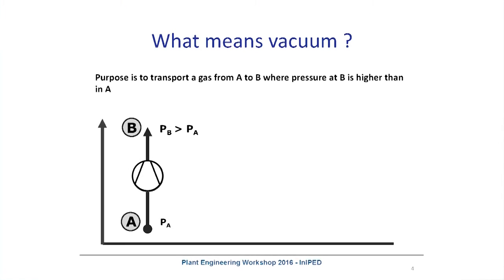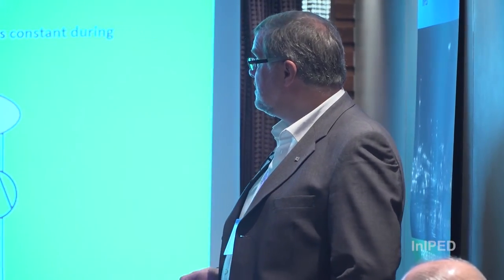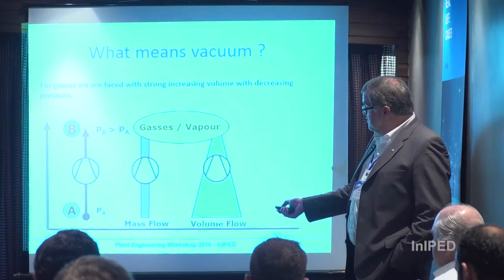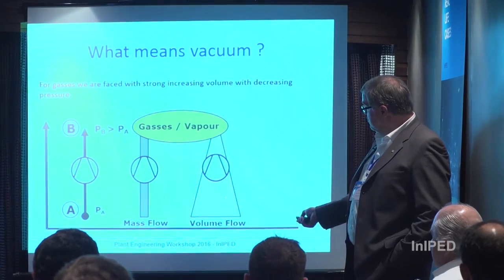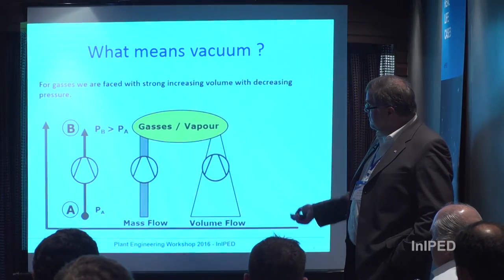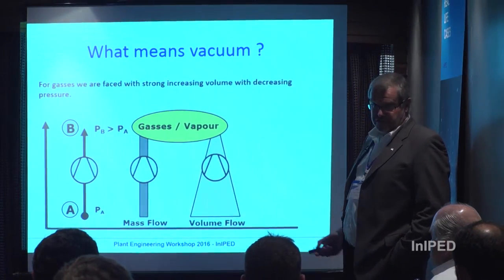What does vacuum mean? In principle, it's the same as with centrifugal pumps — you bring a gas from point A to point B, where the pressure in B is higher than in A. On liquids, we have a constant mass flow and a constant volume flow, because liquids are not compressible. When we talk about gases, the mass flow is also constant, but the volume flow is decreasing with the rising of pressure.